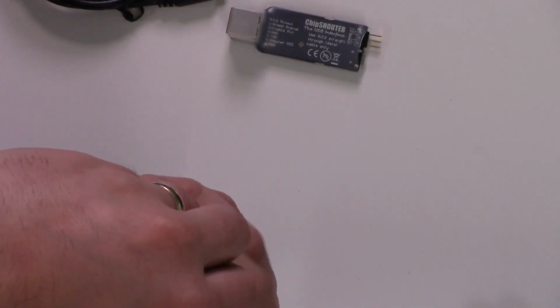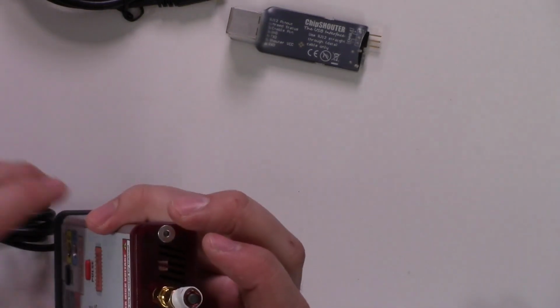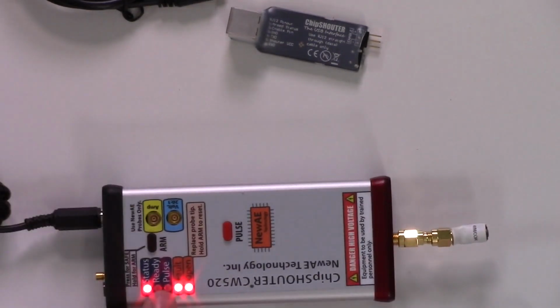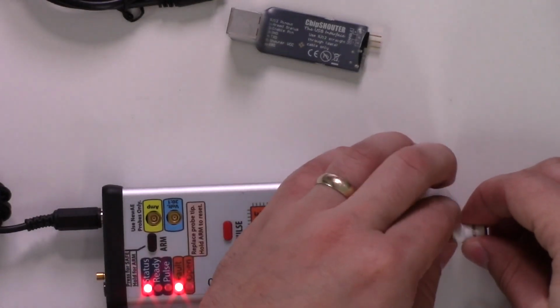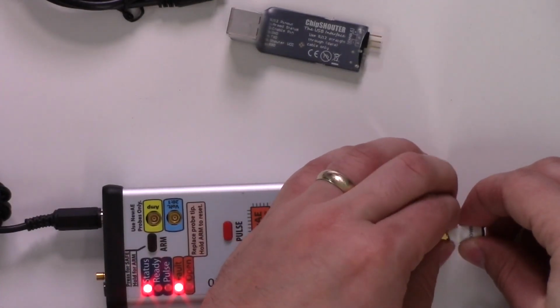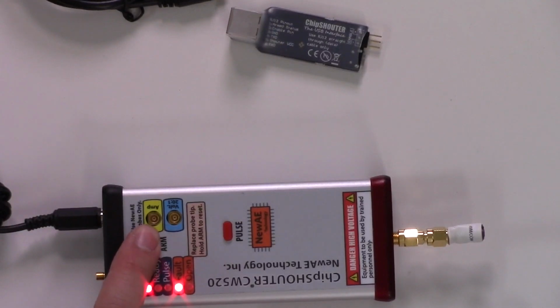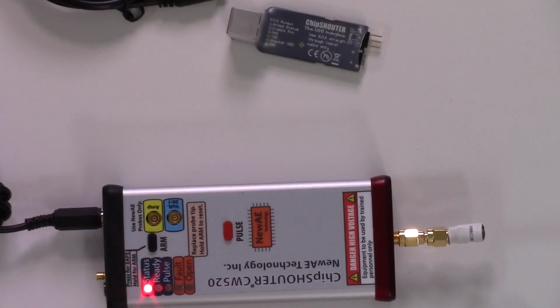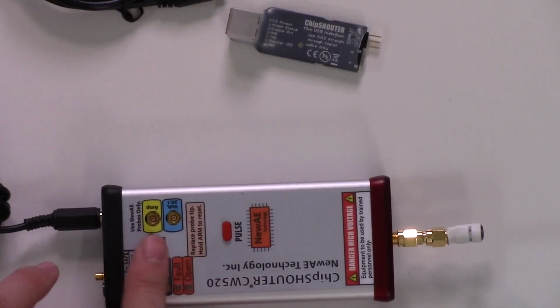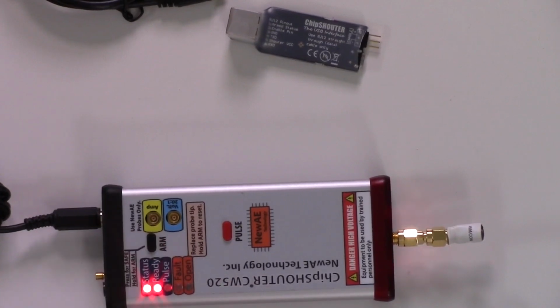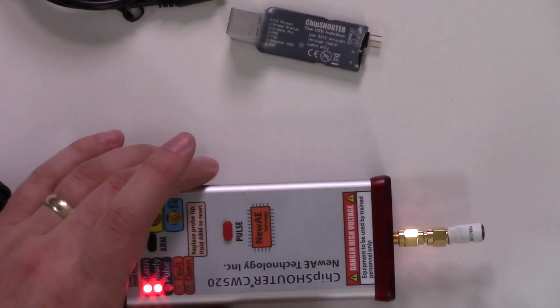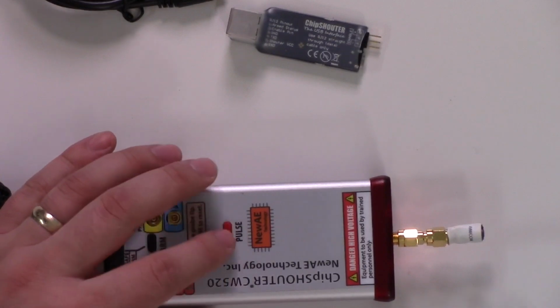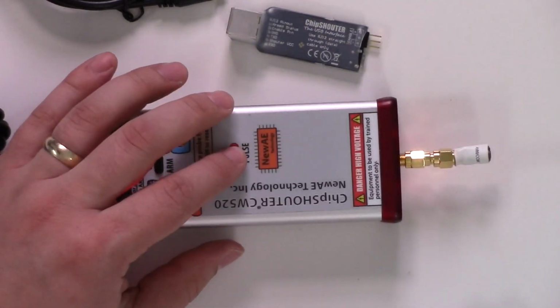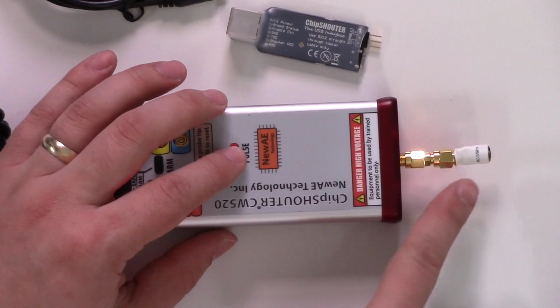right, what's going to happen once it loses contact is it's going to cause a fault condition. So to clear this fault condition, now that we're in a fault condition, we can use the serial port to do that. But I'm just going to hold this down, and we have to hold the arm button for some time to clear the fault. There we go. And that's basically to teach you a lesson not to remove the tip. Now, if we just want to do a basic test, I can just hold this pulse button down. And this is actually inserting faults by discharging into this tip here.